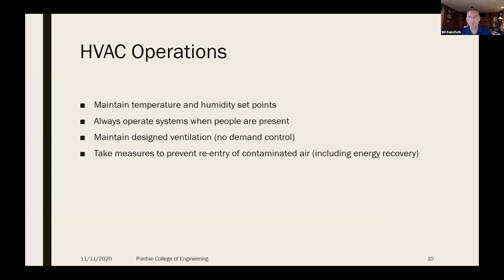For HVAC operations, we can talk a lot about humidity in the discussion, but there is some reason to believe that controlling humidity, particularly at the low end of the scale to 30 or 40%, has some protective value. Systems should always be operated when people are present. Don't shut them off just because it's the end of the business day. And don't use things like demand-controlled ventilation to save energy when that's going to reduce the amount of ventilation.